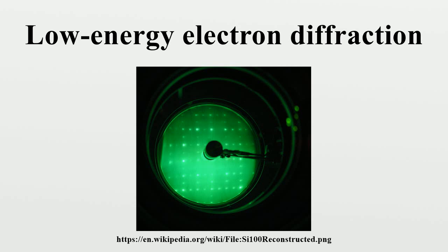Electron gun. In the electron guns, monochromatic electrons are emitted by a cathode filament, which is at a negative potential, typically 10 to 600 V, with respect to the sample. The electrons are accelerated and focused into a beam, typically about 0.1 to 0.5 mm wide, by a series of electrodes serving as electron lenses.